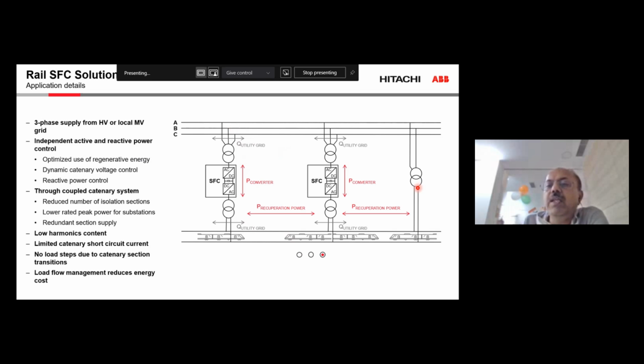When we have one side normal substation fed through the transformer, and we have static frequency converters connected in tandem, we can eliminate the entire network in between, what is called as the neutral zones. So the entire railway network to the stretch of say 100-200 kilometer can be considered as a single network. So we don't have to do any kind of disconnection of the internal power network from the catenary feeding to the railway internal engine. So it can be seamless flow of the current from one section to the other section.